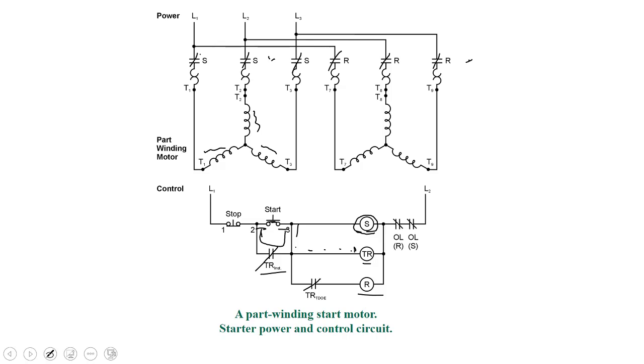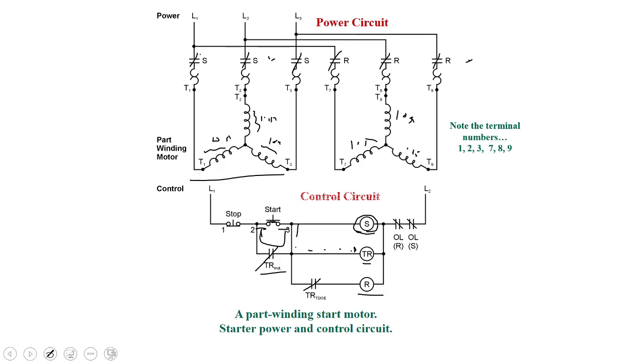So how does this reduce current? Well, think of these two. If there are 10 ohms of opposition in each one, and then I put another 10 ohms in direct parallel with them, now the overall opposition in the circuit is down to 5 ohms. So the current is much less with just one. Now we do have a risk of trying to start this motor on just one winding, depending on how heavy the load is. So there are some rules with this that we want to follow. Note the numbering, we'll come back to that. So it's 1, 2, 3, 7, 8, and 9.